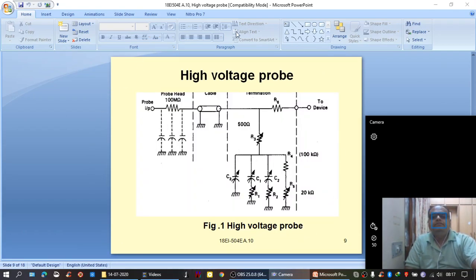And the internal circuit for a high voltage probe would be like this. Here is the tip, 1000 ohms, 100 mega ohms probe head to withstand the high currents. And at high voltages, there is every possibility of stray capacitances also affecting. In order to compensate for this stray capacitance loss, a compensation circuit is provided here in the termination portion. So whatever loss has occurred is recovered here, right? So probe head, then cable.